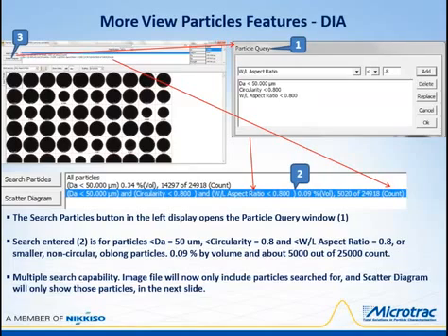Note in the highlighted search, callout 2, this group of particles make up only 0.09% of the entire sample volume and about 5,000 particles by count of about 25,000 in the sample. And note in the search listed above the highlighted one, where the width to length criterion is left out, this group made up 0.34% by volume of the sample and had a count near 14,000.